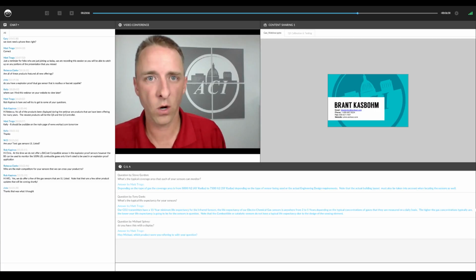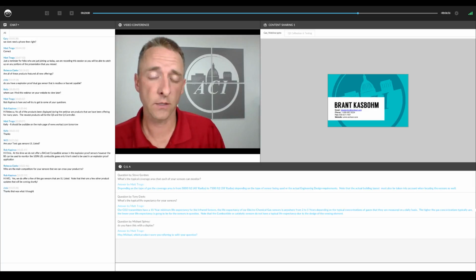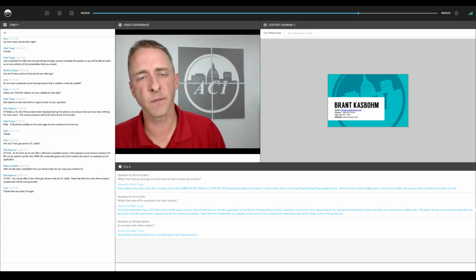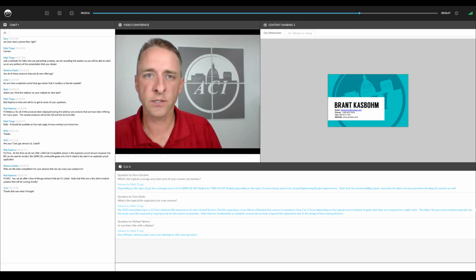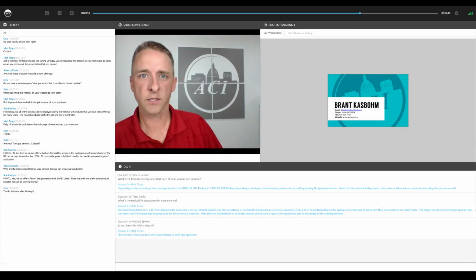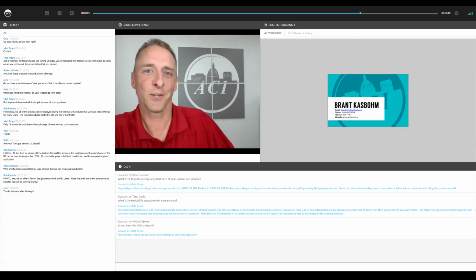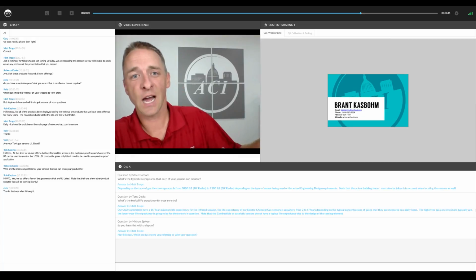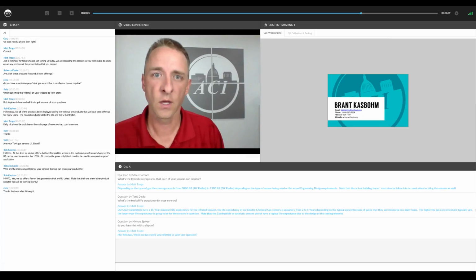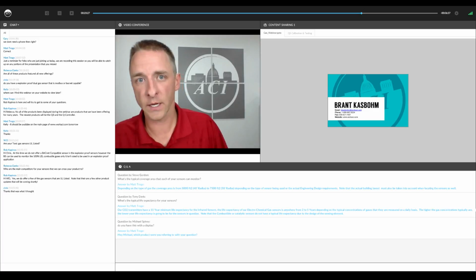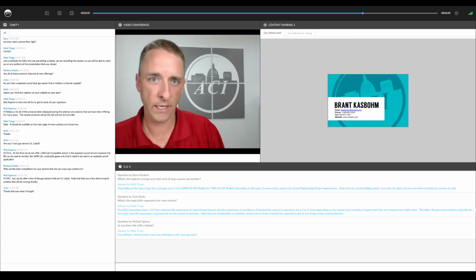There is some debate about this in industry. For example, NO2 is present in diesel exhaust, and so when exhaust is first exhausted from the car, it'll rise because it's hot, but as it cools, the gas will settle, and typically that's where people are working on or under vehicles. So we base it on the actual chemical weight of the gas. That's where we base our mounting height, and not on any changes due to temperature of the gas.